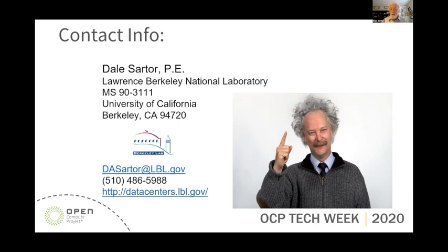Right, and as I mentioned, when you have your free cooling in series with your compressor-based cooling, you'll get a greater percentage of the cooling the warmer the return water temperature is. I think the vision is to run our data centers so warm that we will use no electricity for compressors and no water for evaporation, that we can cool anywhere in the world just from the ambient air. And I think that's a vision that we'll see if it's reality as we go into this panel discussion phase of today's session.